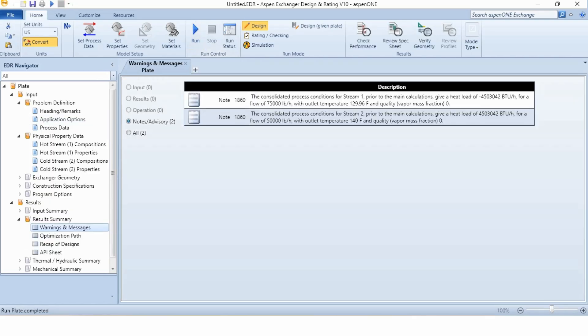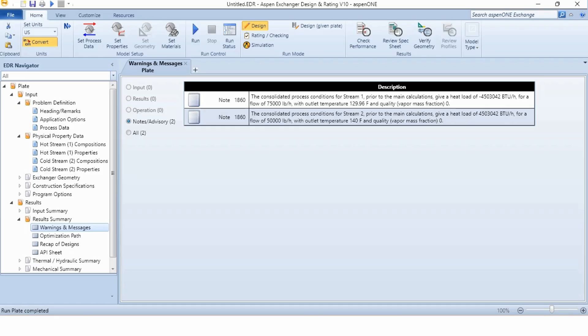You can see the results are completed. There are two notes provided to us. Number one is the consolidated process conditions for stream 1. Prior to the main calculations, gives a heat load of minus 4,503,042 BTU per hour for a flow of 75,000 pounds per hour. With outlet temperature, this outlet temperature is computed by Aspen. We had given the inlet temperature as 190 degree Fahrenheit, so the outlet temperature is 129.96 degree Fahrenheit. The vapor mass fraction is 0.